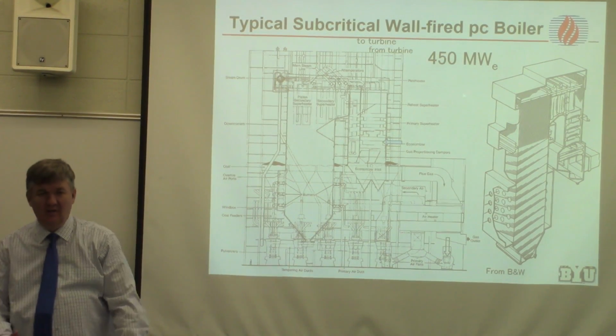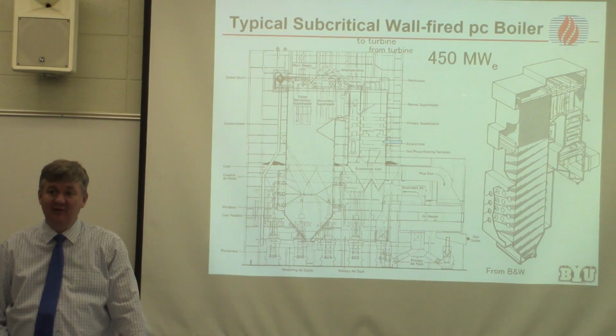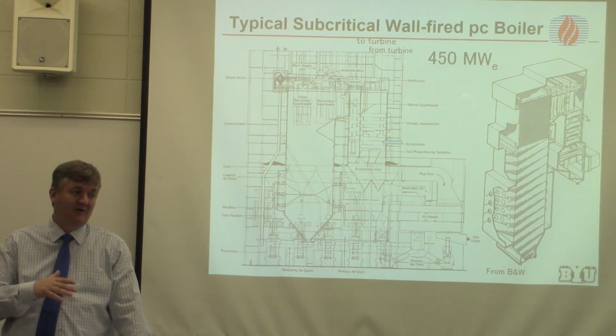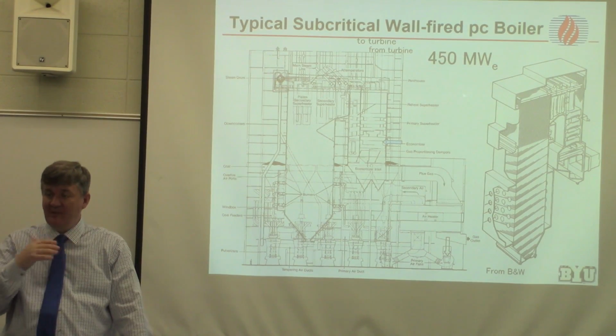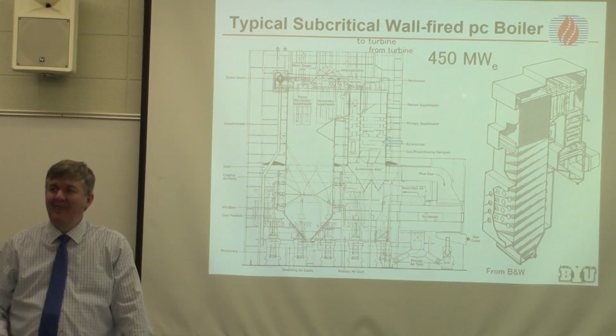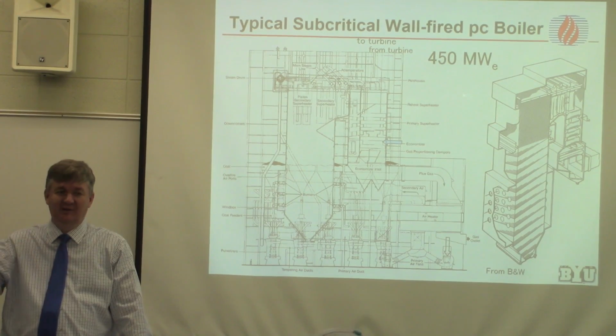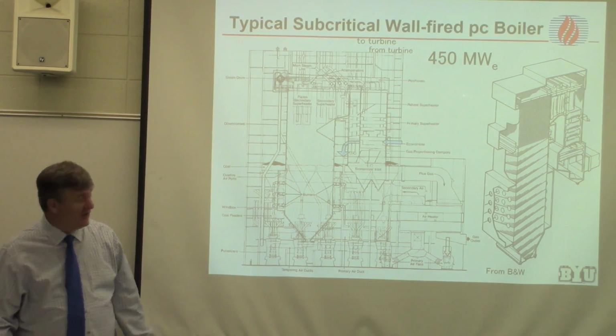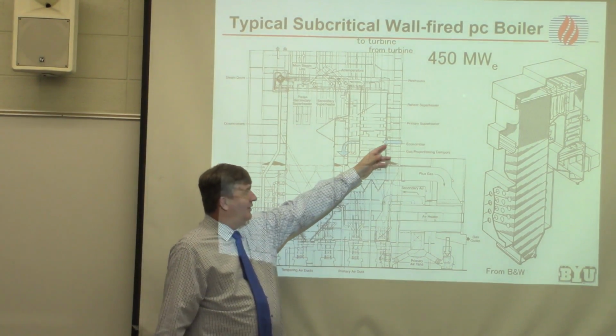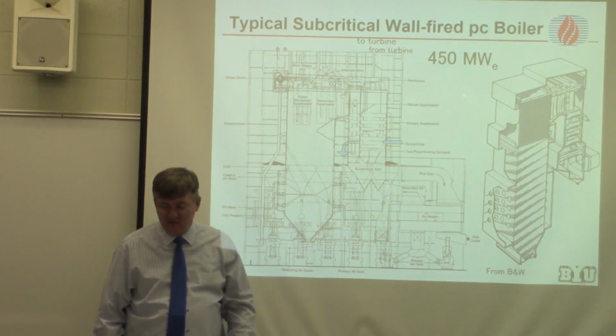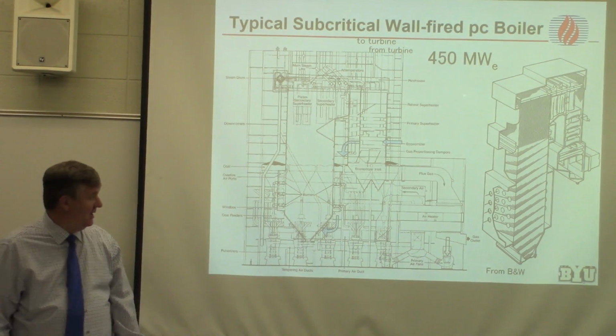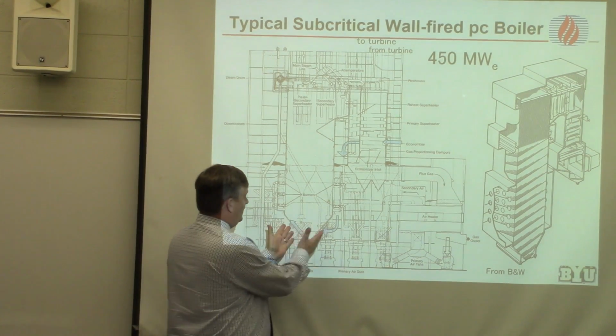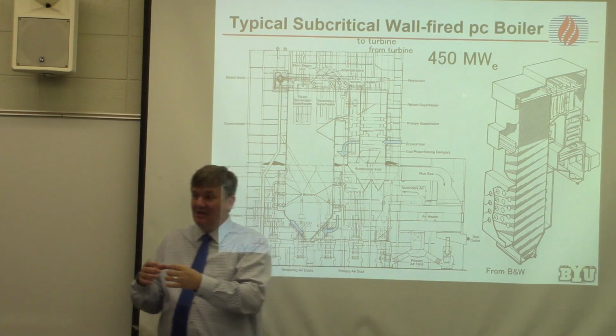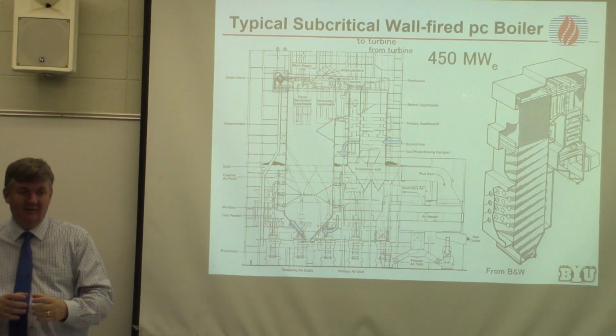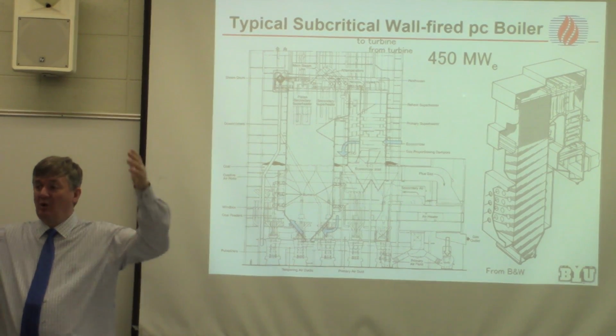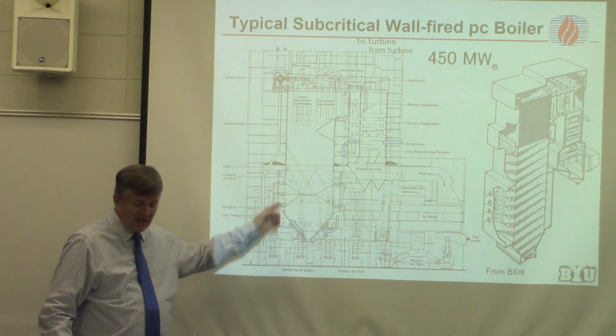It's at high pressure, typically 200 to 250 bar. The critical pressure of water is about 220-some bar. So at 200 it's just subcritical, at 250 it's supercritical. So it comes in at very high pressure in very large quantities of water. It's warmed up but not boiled, and then comes down into what they call water walls, which are these tubes that I mentioned. These are just high pressure tubes that are welded together and form the walls of this boiler. And the water goes up the side of the walls of the boiler.